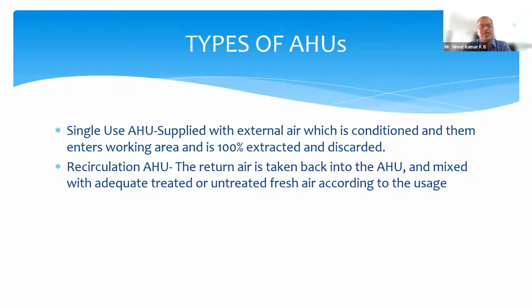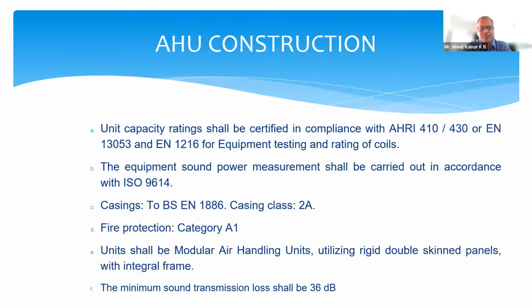There are treated fresh air AHUs dedicatedly used in many places, which is another good way of doing it. You have an AHU which takes the fresh air needed for the areas, and then it gives the treated fresh air to all the other recirculating AHUs. So this is also a good method of having a 100% fresh air AHU giving treated fresh air to all the recirculating AHUs.